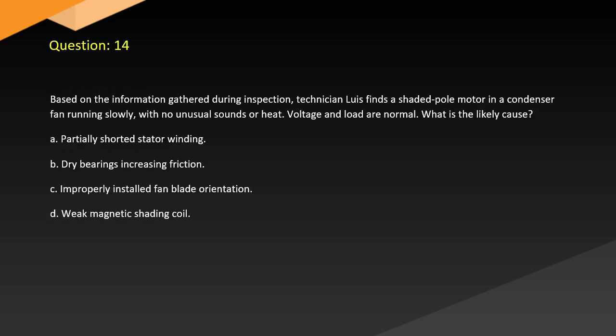Question 14. Based on the information gathered during inspection, technician Lewis finds a shaded pole motor in a condenser fan running slowly with no unusual sounds or heat. Voltage and load are normal. What is the likely cause? A. Partially shorted stator winding. B. Dry bearings increasing friction. C. Improperly installed fan blade orientation. D. Weak magnetic shading coil.